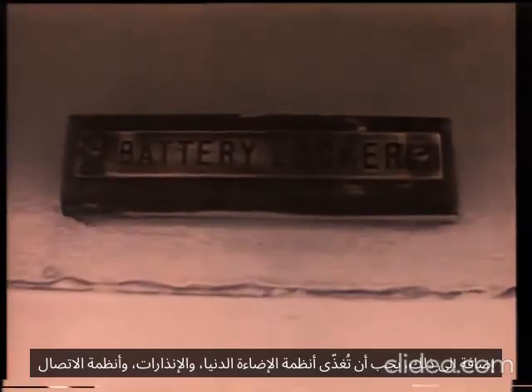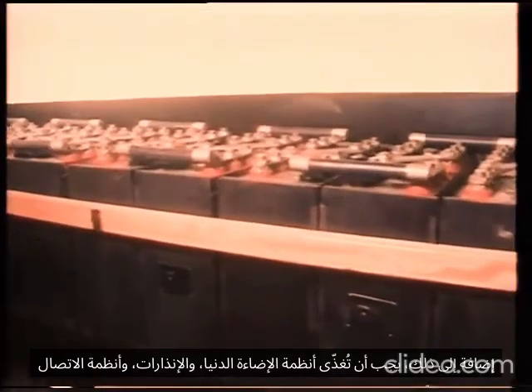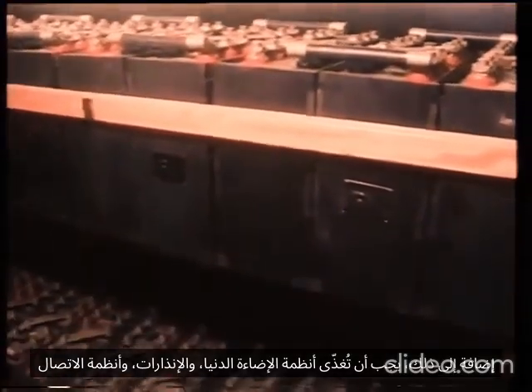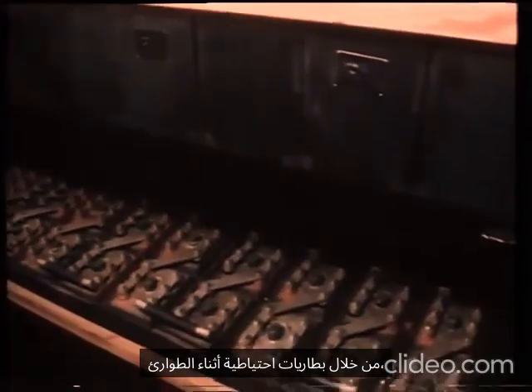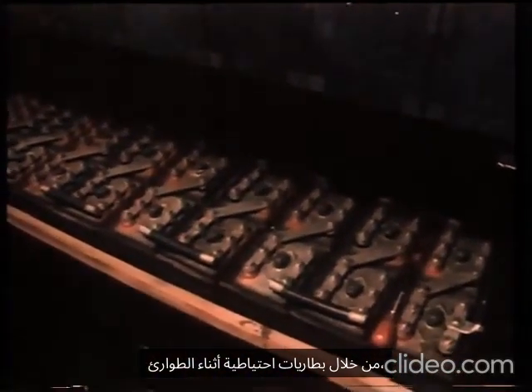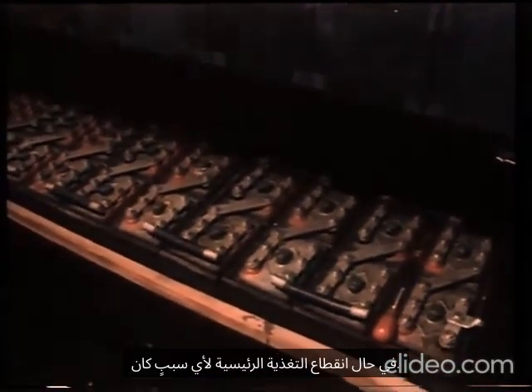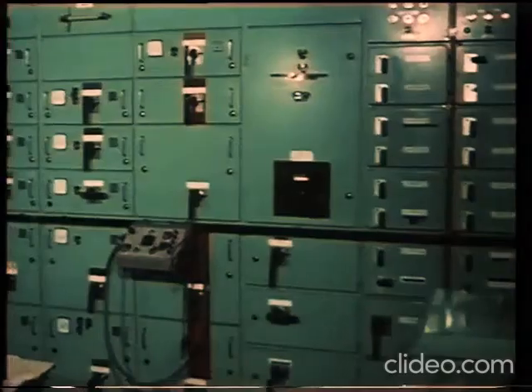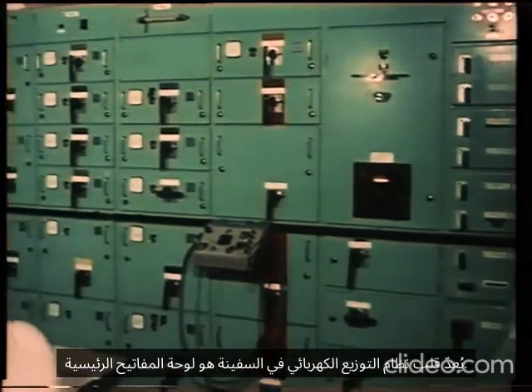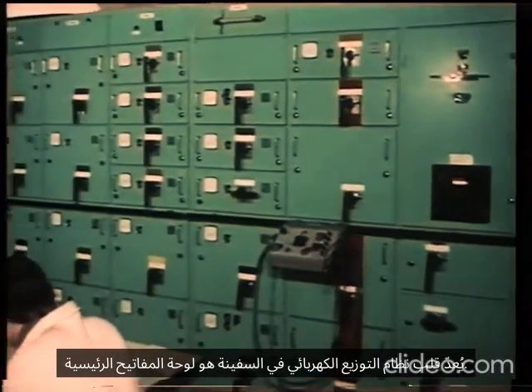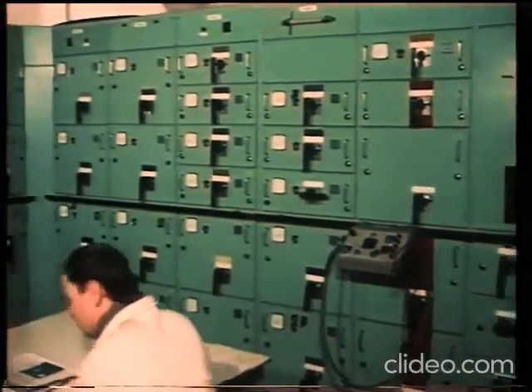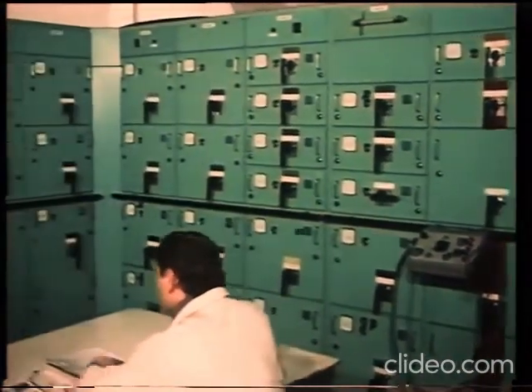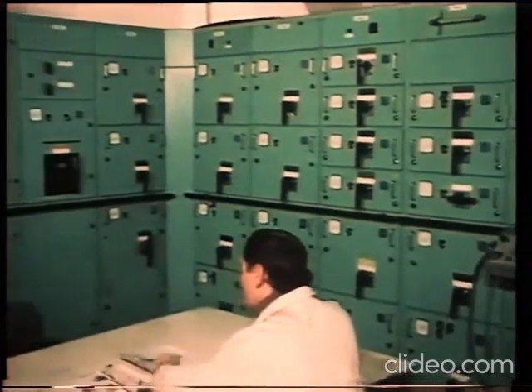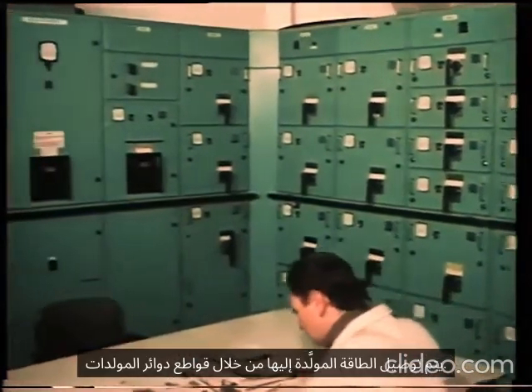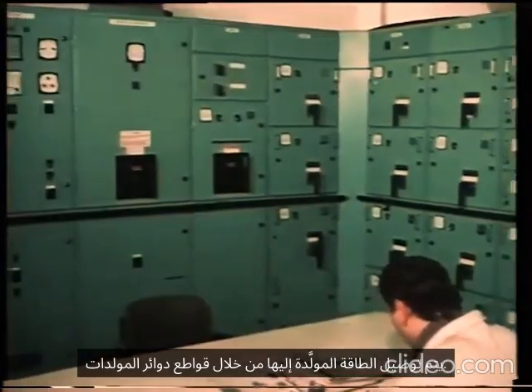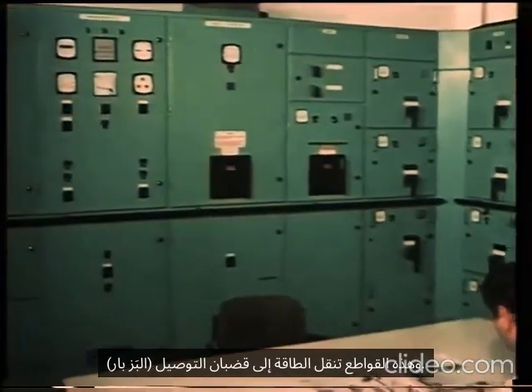In addition to this, a minimum level of lighting, fire and general alarms and communication systems must be supplied by a battery supply during an emergency, when the main supply is interrupted for any reason. The heart of a ship's electrical distribution system is the main switchboard. The generated power is connected to it by the alternator circuit breakers, which connect power to the bus bars.